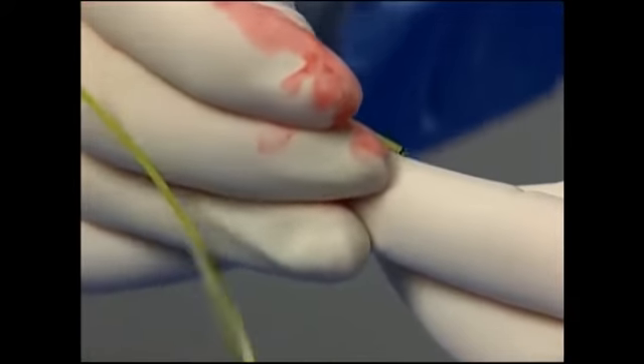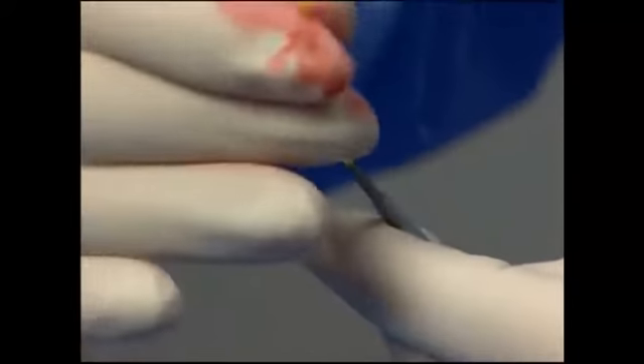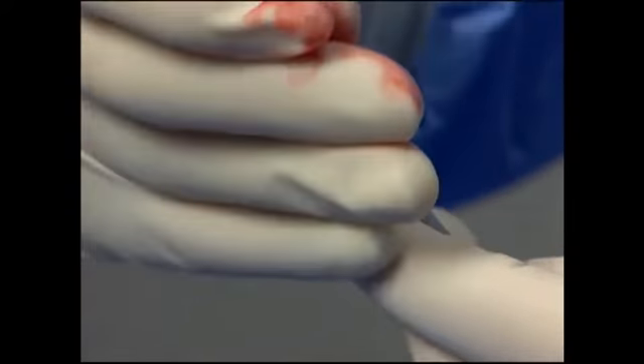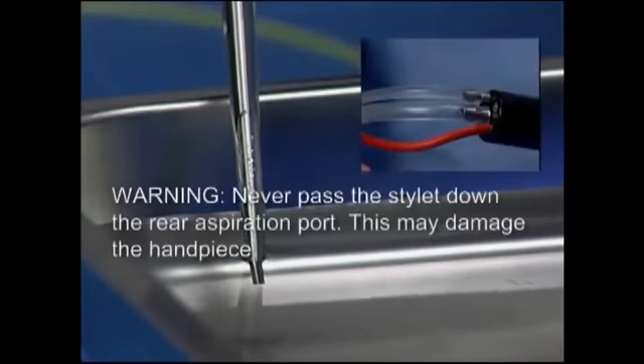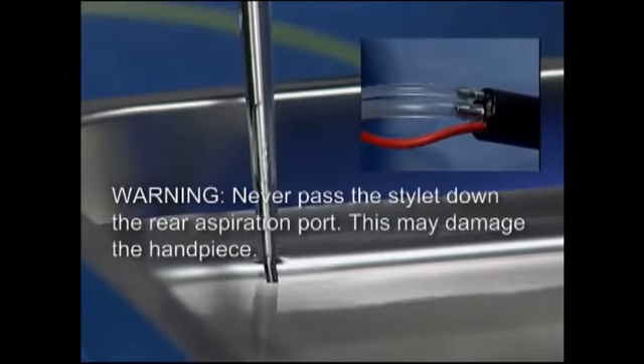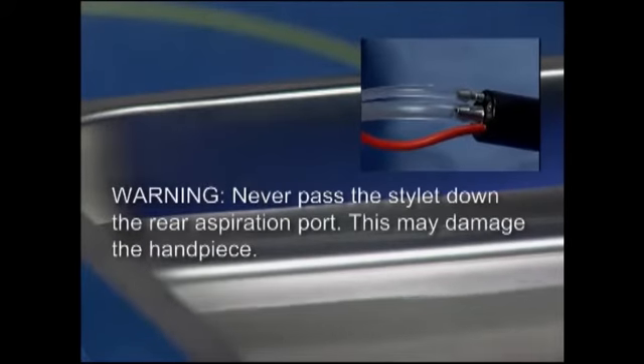Should a blockage occur in the handpiece, the stylet should be passed through the tip and up the central aspiration channel until the blockage is cleared. Then flush the tip in sterile saline as before. Never pass the stylet down the rear aspiration port. This may damage the handpiece.